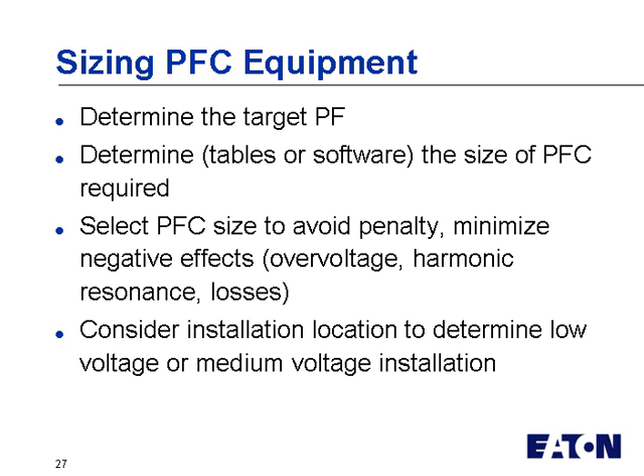And again, that's pretty readily available today. You select the type or the size to avoid the penalty, but secondly, and importantly in many cases, to minimize the negative effects like overvoltage, for example, or harmonic resonance, which we're going to talk about later, or losses through the system. Overvoltage is an important issue. If your load is on all day and then off at night, you may apply a capacitor and the voltage might go very high at night and you could have other problems.